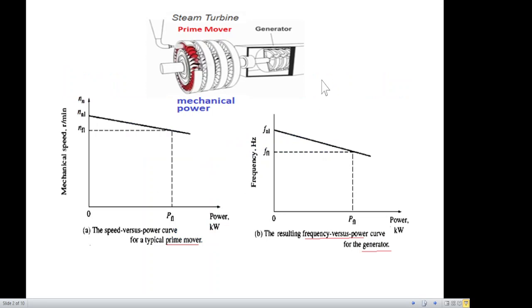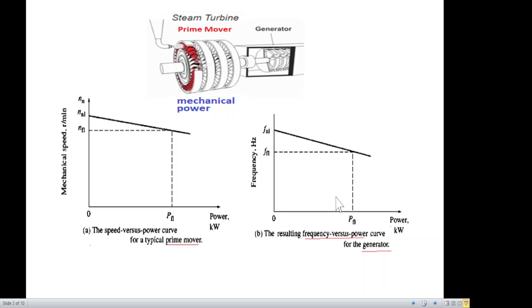Before we start, let's recall the prime mover connected with the generator. The graph discussed shows the speed versus power curve — this is the power generated by the load and this is the speed of the prime mover. This graph is also called the droop curve. As the power demand increases, the no-load speed of the generator or prime mover will reduce. Because they are connected, the same graph applies; the only change is that in case of a generator, instead of speed, we talk about frequency.